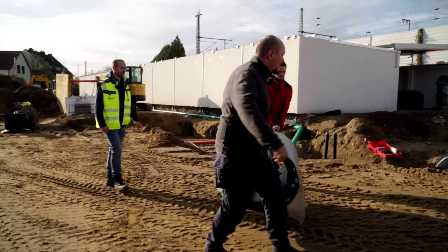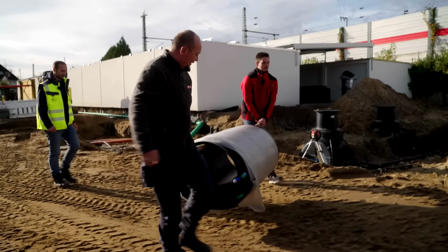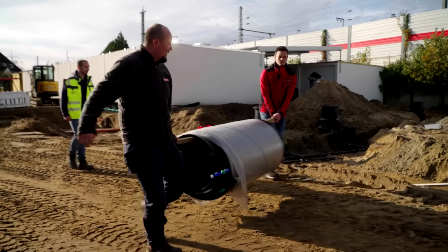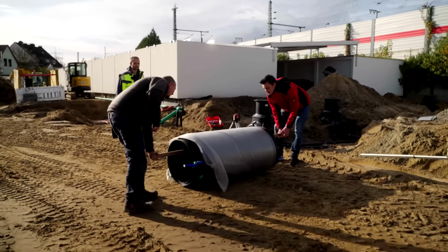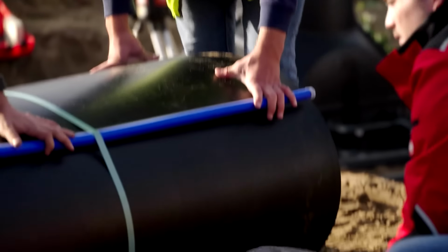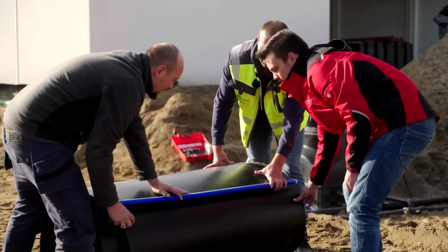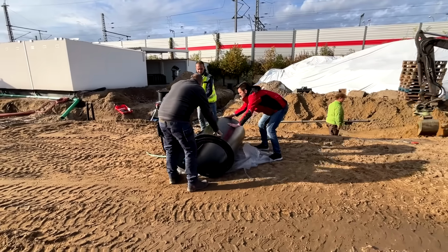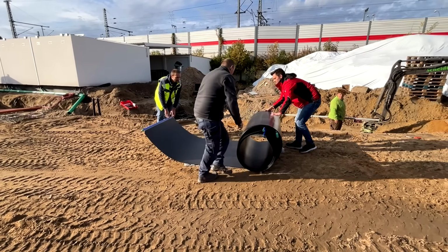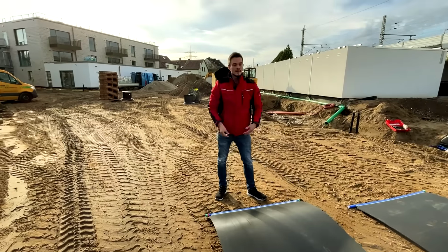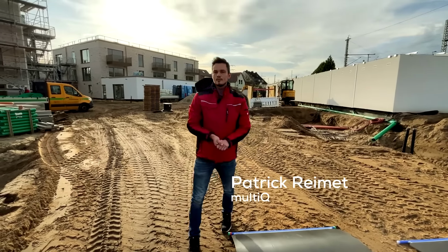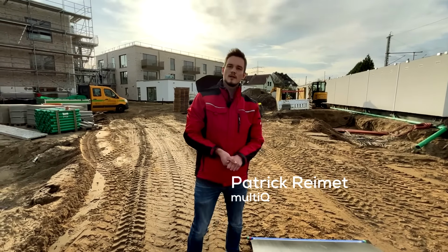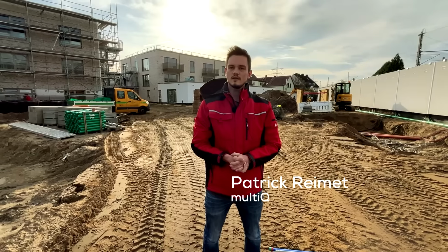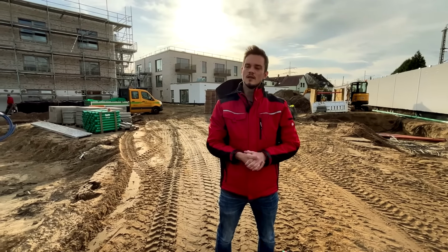Workers are installing special plastic mats. This will allow the soil to absorb heat during the summer and release it when needed. A mixture of water and glycol, known as brine, will later flow through these so-called ground absorbers. The ground heat exchanger is made of polypropylene, which is highly conductive and has very thin walls, allowing the heat from the ground to be transferred directly to the brine.